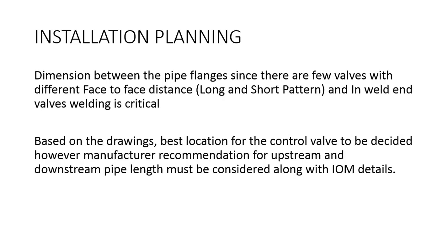Another parameter which is equally important in installation planning is the dimension between the pipe flanges. Since there are valves with different face-to-face dimensions, that is, it could be a long pattern or a short pattern, or in weld end valves, welding is critical. So you need to know the distance between the pipe flanges. Hence, based on the drawing, the best location for the control valve is decided. However, manufacturer recommendation for upstream and downstream pipe length must be considered along with IOM details.